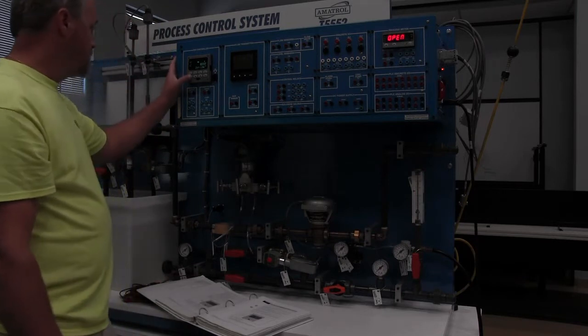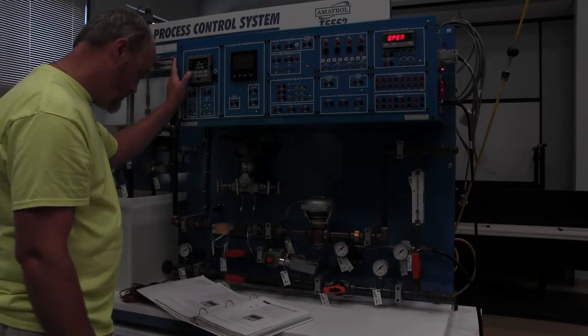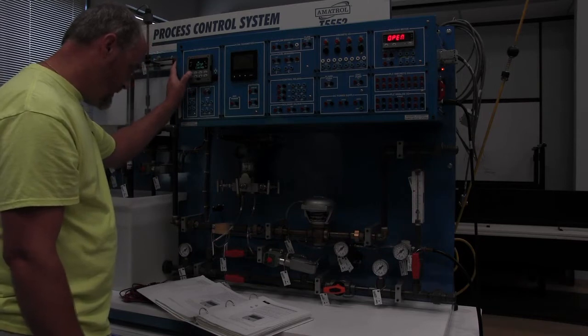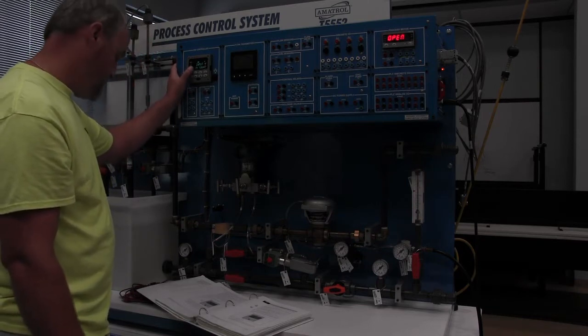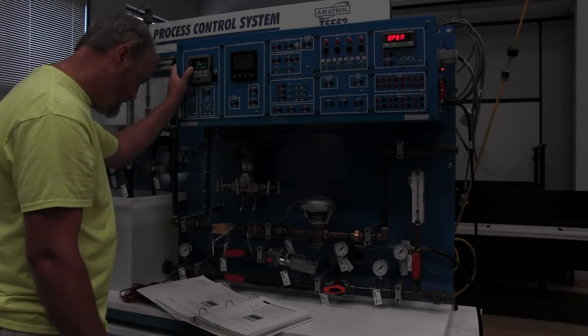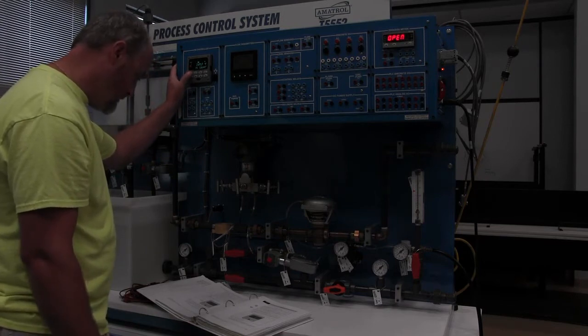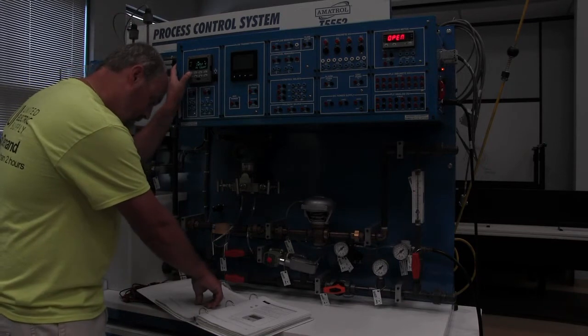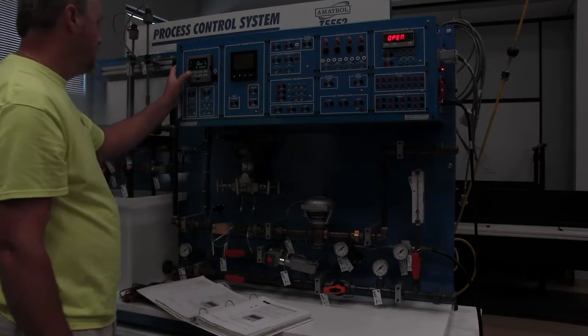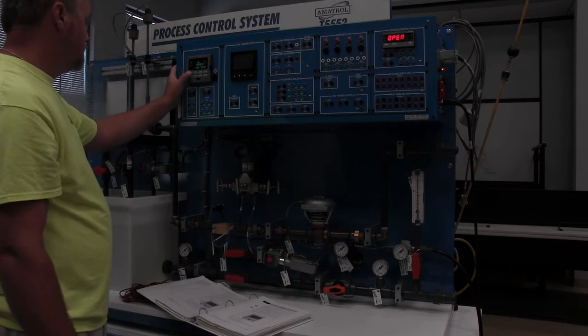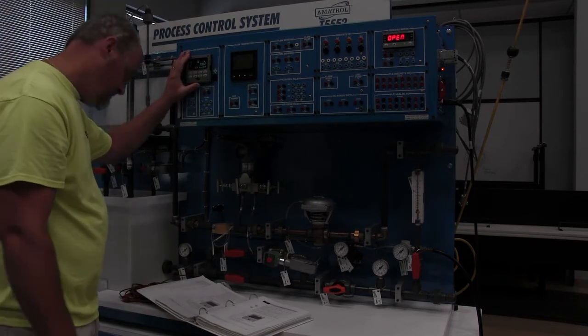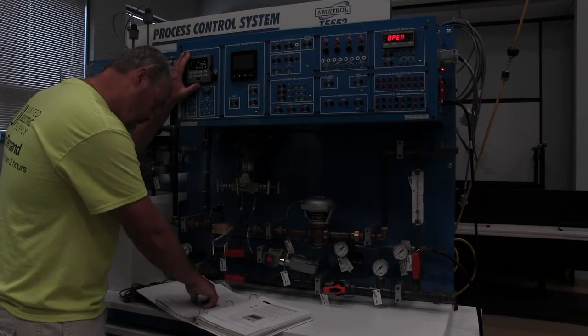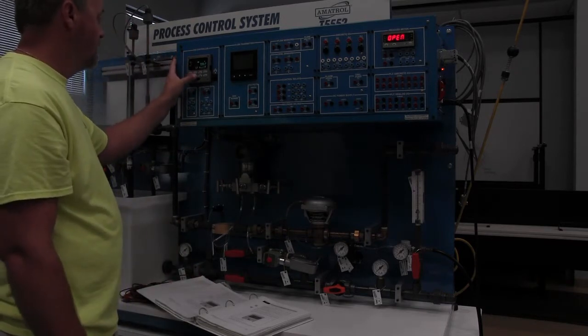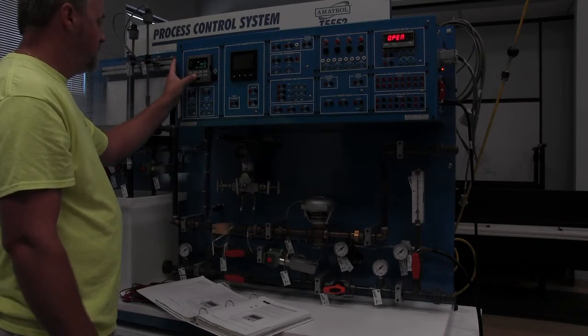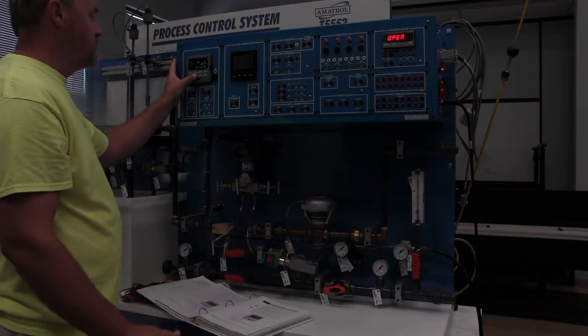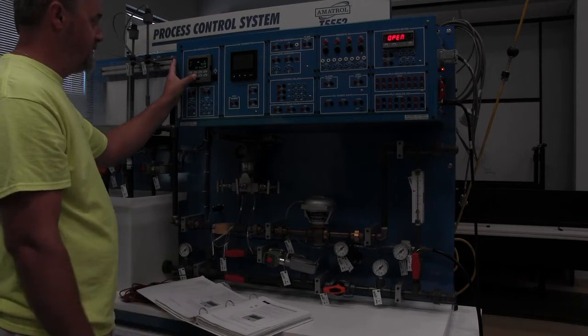And now we're going to go to the control setup. In the control group, we're going to be looking for PV source, which is the first one that comes up. Use the navigate until we see the set point high limit. Set point high limit. We're going to change that to 24. Basically what we're doing right now is just setting this controller up for the parameters that they're asking for.